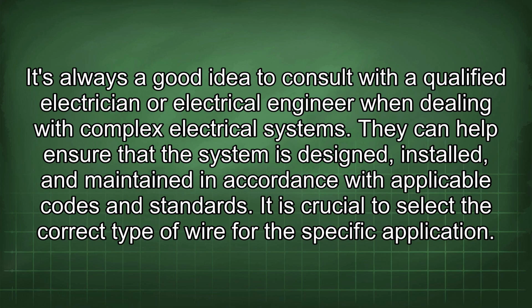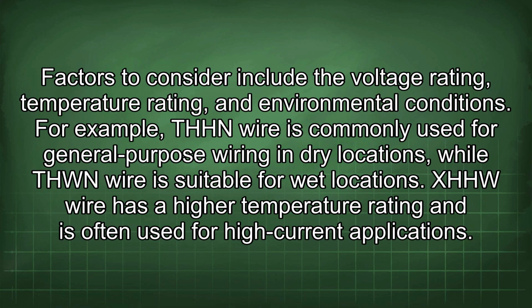It is crucial to select the correct type of wire for the specific application. Factors to consider include the voltage rating, temperature rating, and environmental conditions. For example, THHN wire is commonly used for general-purpose wiring in dry locations, while THWN wire is suitable for wet locations. XHHW wire has a higher temperature rating and is often used for high current applications.